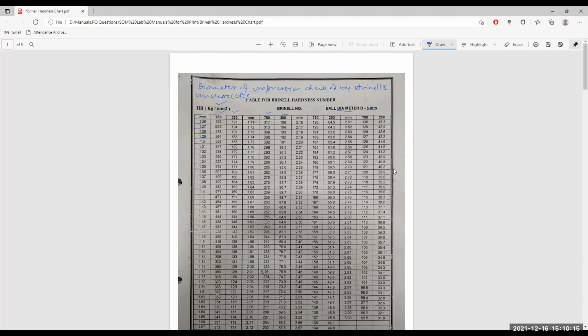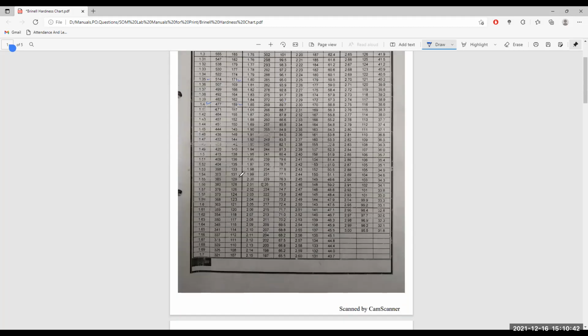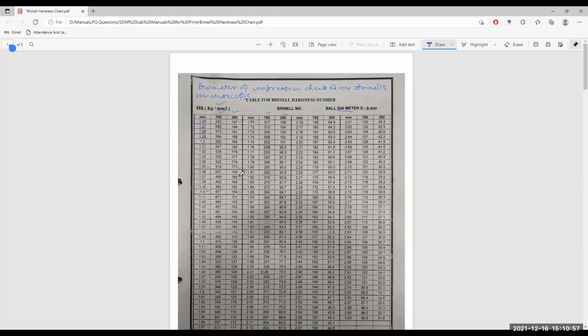For say a 250 kg weight, if the impression diameter is 1.35 millimeter, the hardness will be 171. For the same weight, if the diameter of the impression is 1.4, the hardness will be 151. So this is the hardest material here, that is 197 Brinell hardness, and it goes on reducing, so that at the impression diameter of 1.7, a hardness of 107 Brinell is achievable. And hardness can be reduced even further.